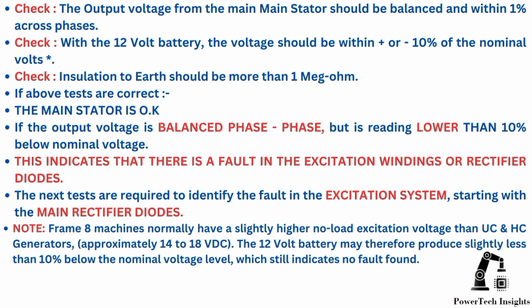If the output voltage is balanced phase to phase, but is reading lower than 10% below nominal voltage, this indicates that there is a fault in the excitation windings or rectifier diodes. In the next video, I will provide a comprehensive guide on the next tests required to identify the fault in the excitation system, starting with the main rectifier diodes. Note, Frame 8 machines normally have a slightly higher no-load excitation voltage than UC and HC generators, approximately 14 to 18 VDC.